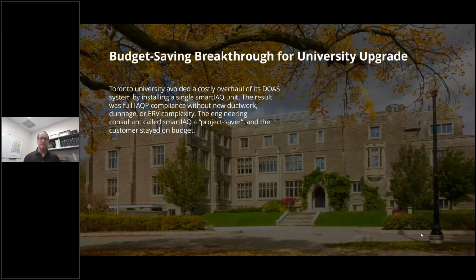This job happens to be just north of us here in the Greater Toronto market. This was a university; they had a theater that they were expanding. The existing DOAS unit was sitting on dunnage, had a certain electrical supply, and so on. But they were expanding the theater, and the engineer was trying to figure out - the unit got so big that the dunnage was going to have to get upsized and reinforced. It was going to require new electrical service, and they were going to have to provide new duct penetrations.